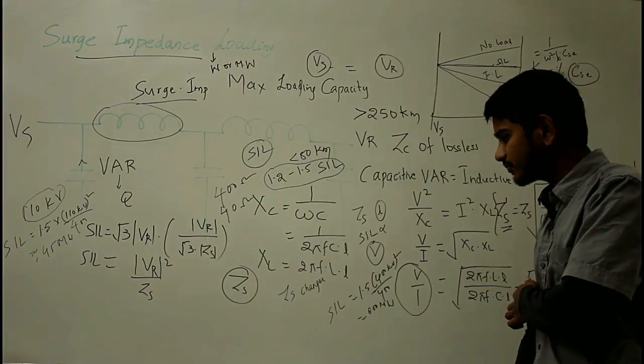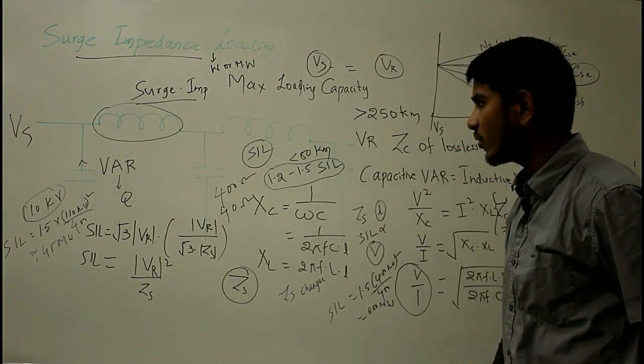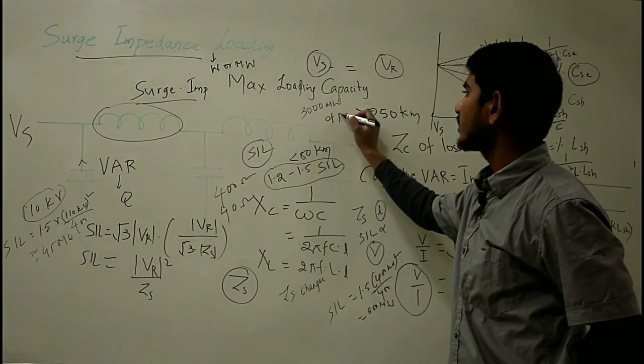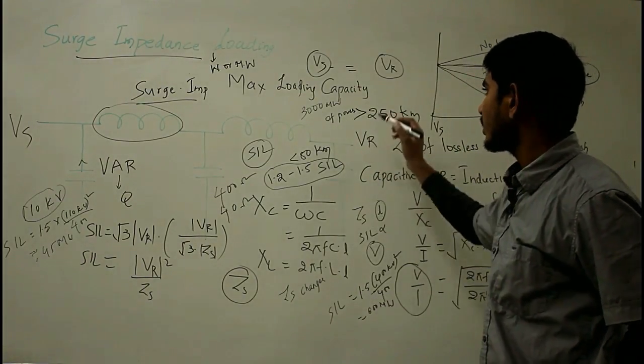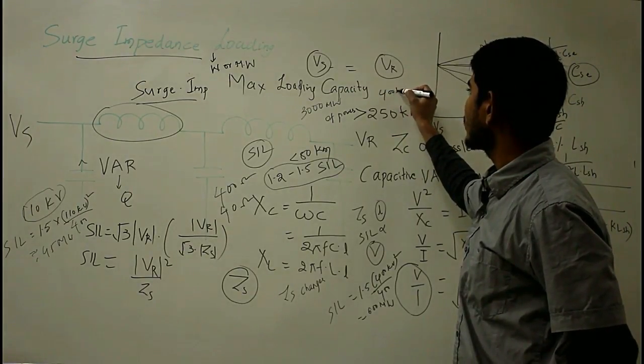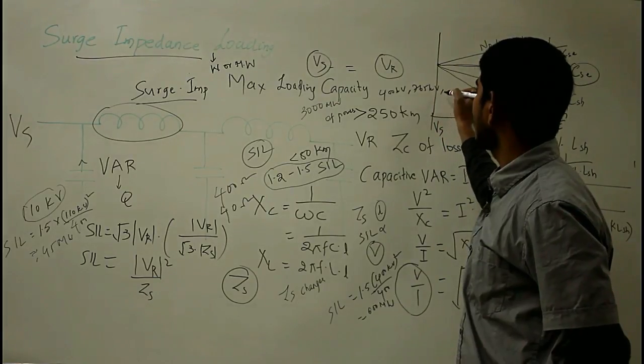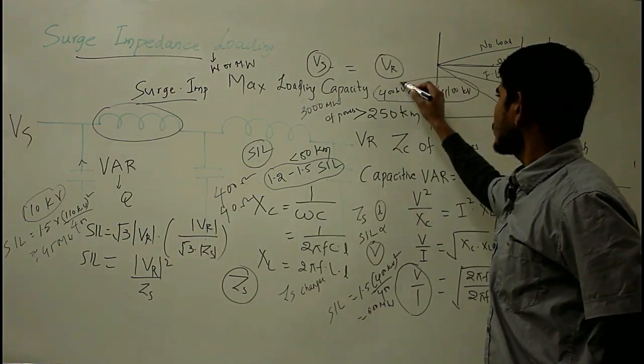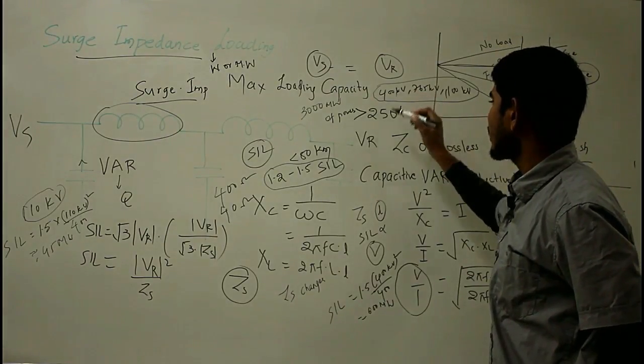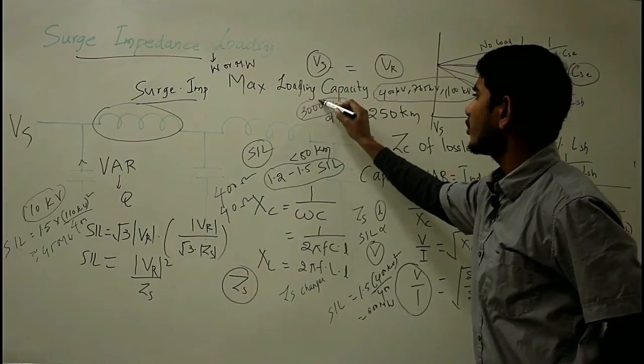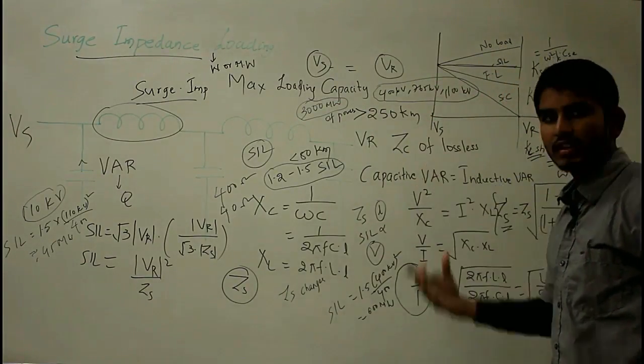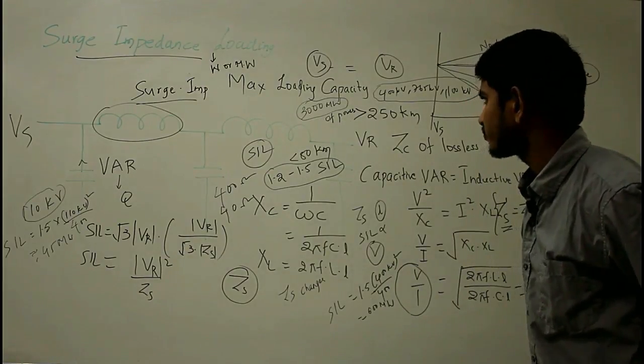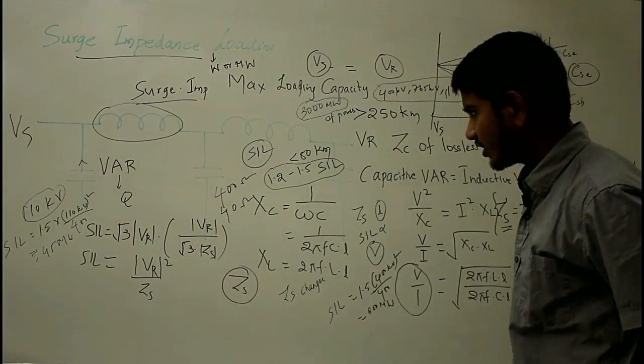For a 400 kV line, SIL = (400 kV)² / 400 ≈ 400 MW, and with a loading factor of 1.5 it is around 600 MW. For any given line voltage you can determine the loadability of the line. Alternatively, you can calculate the number of lines required to transfer a given power — say 3000 MW — at various voltages such as 400 kV, 765 kV, or 1100 kV.